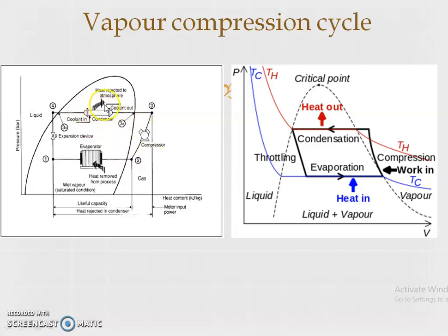The condenser, as you generally know, is a heat exchanging process. Here the heat is rejected to the atmosphere with the help of cooling from the seawater or with the help of the fan. We exchange the heat in this condenser process. After that, the high pressure liquid passes through the receiver tank and the thermostatic expansion valve. It goes through process 4 to 1, the expansion device.